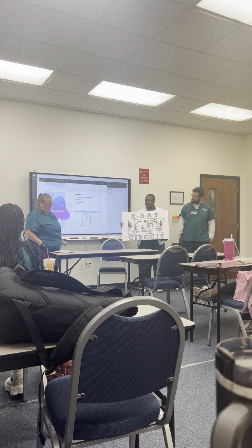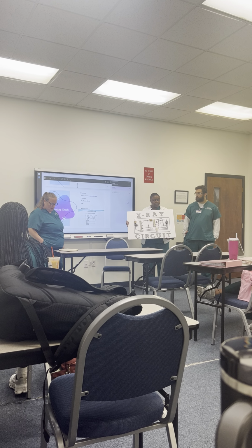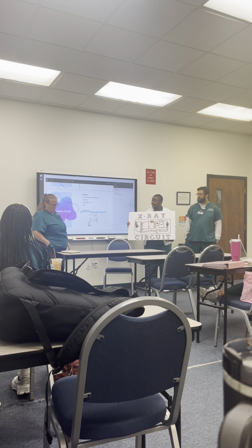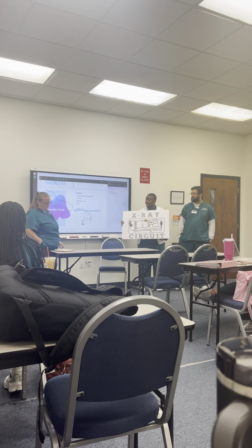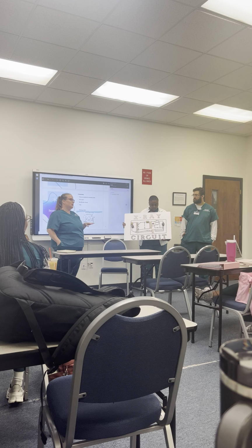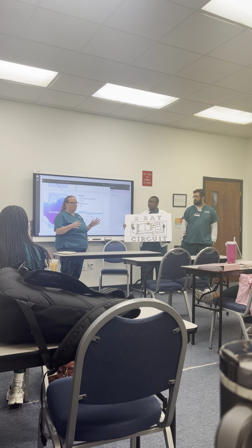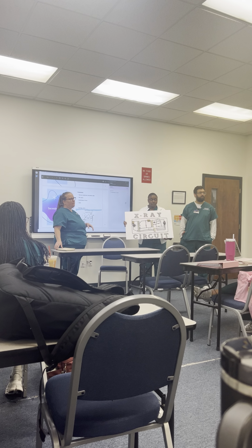This makes the current flow in one direction when it transfers from AC to DC. Without this circuit, or if it malfunctions, the tube wouldn't function properly. So if it doesn't convert to DC, then the current is not flowing in one direction, and that would basically explode the tube and make it malfunction.